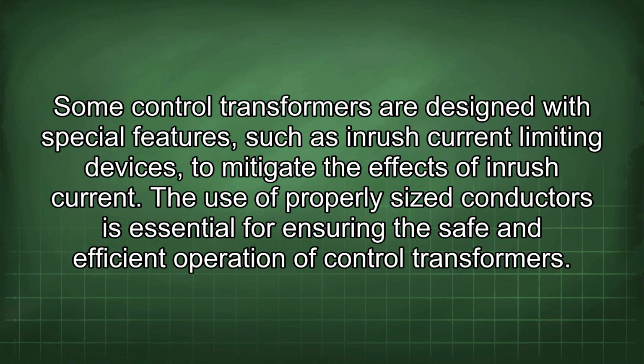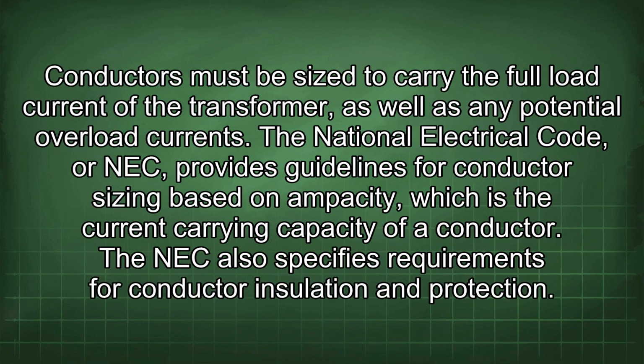Some control transformers are designed with special features, such as inrush current limiting devices, to mitigate the effects of inrush current. The use of properly sized conductors is essential for ensuring the safe and efficient operation of control transformers. Conductors must be sized to carry the full load current of the transformer, as well as any potential overload currents. The National Electrical Code, or NEC, provides guidelines for conductor sizing based on ampacity, which is the current carrying capacity of a conductor. The NEC also specifies requirements for conductor insulation and protection.